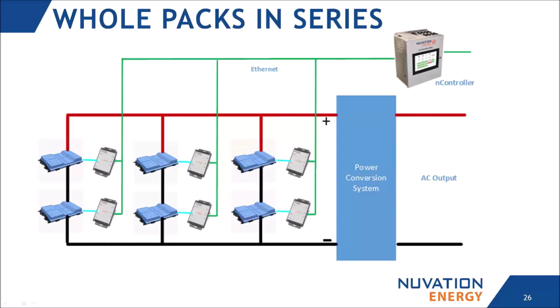But there are some concerns when you do that - achieving these higher stack voltages means you're open to higher short circuit currents. If you short the stack under high voltage, you get higher short currents. The insulation of the packs may not be sufficient - you have to work with the manufacturer to understand their insulation capabilities and whether you're capable of doing series connections of them.